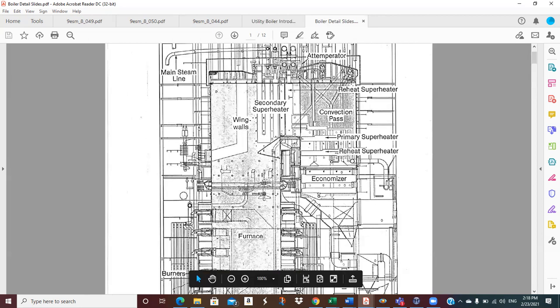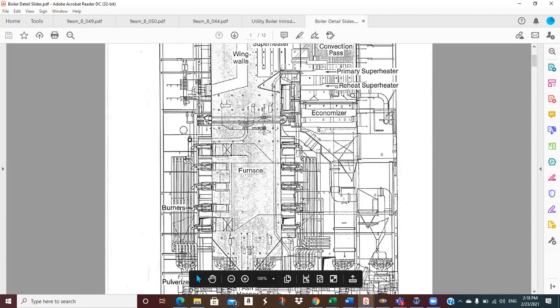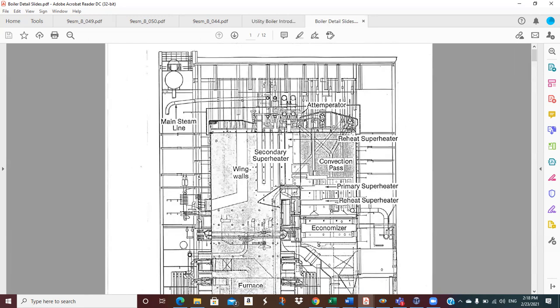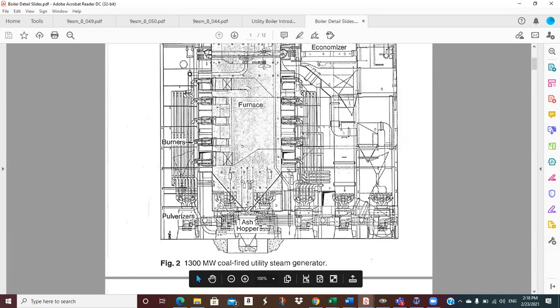The furnace itself is just lined with tubes. This is called water wall tubes. The steam is generated in these water wall tubes. So this furnace area is a big open box, and all of the walls are just tubes packed up right next to each other. And we take liquid water out of the drum down to the bottom of the boiler, and then that water is fed into headers down here that feed all of these individual water wall tubes.